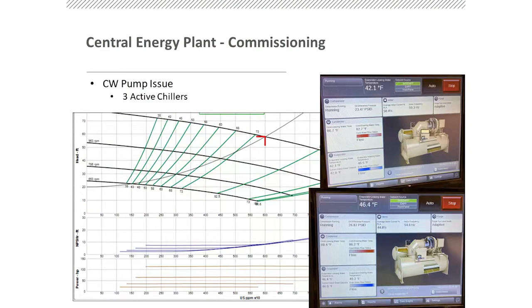Now, flow balance, three chillers running. This was an interesting piece, and I'll touch on it. The original pre-design that the owner went out and got was from an individual in the Orlando area who has done a lot of extremely large chilled water plants for utilities. In his design, one of the things was that the control valves on the chillers shall be modulating. If I've got four in one section and three on the other and I can have any combination, how do I actually balance the flow, whether I'm running one and six, or one and two?